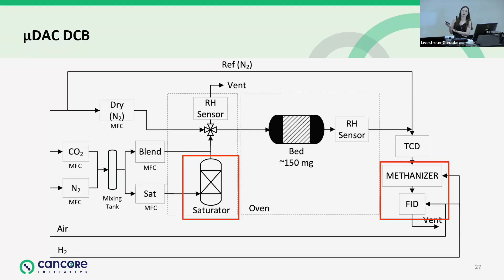I'll say what makes this system special is the fact that the saturator is inside a thermostated oven, which means we can control the relative humidity quite well. We can make sure that we can get to that 95 to close to 100% RH at the different temperatures we want to study. And the other thing that's very important about this instrument is our detector train. It is very hard, when you're trying to measure very dilute concentrations of CO2, for your detector to not be affected by your water. So this methanizer and FID combo lets us see down to, I'll show you, about 0.1 ppm.